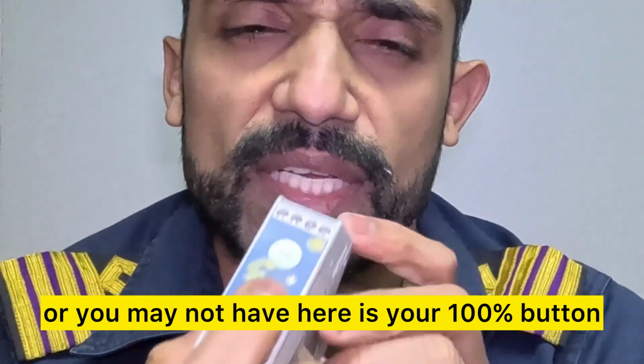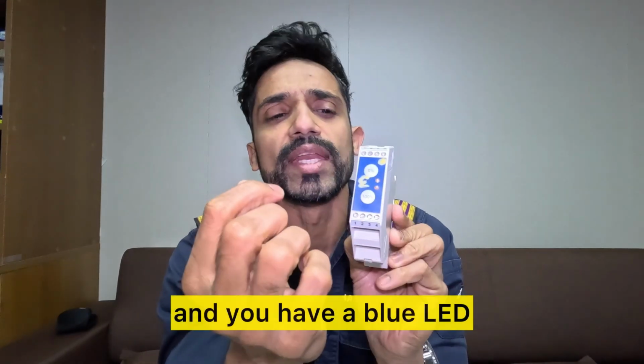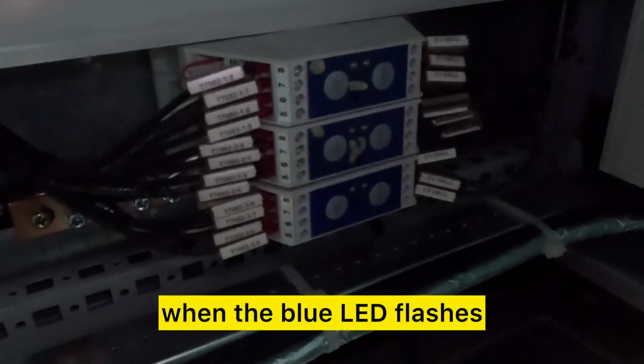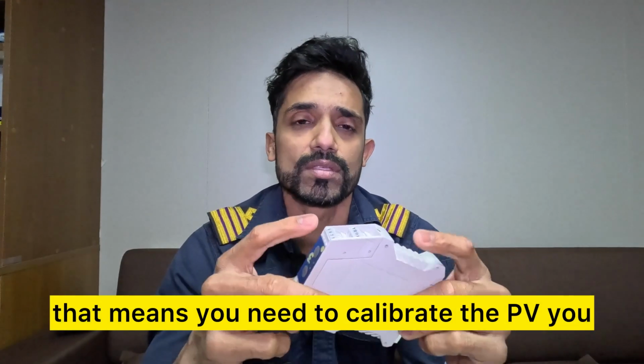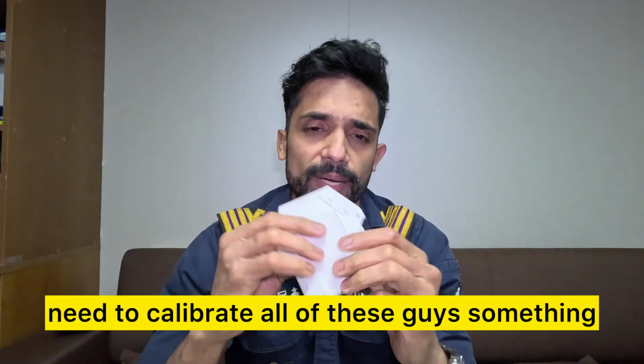Here is your 100% button and this is your 0% button, and you have a blue LED. When the blue LED flashes while connected in the system, that means you need to calibrate the PVU. You need to calibrate all of these.